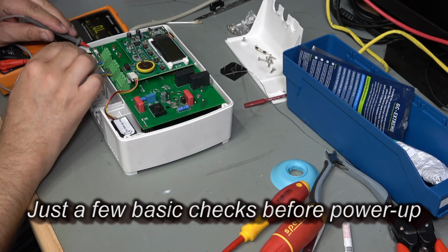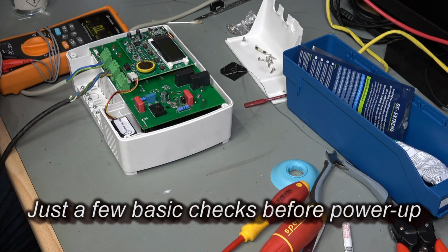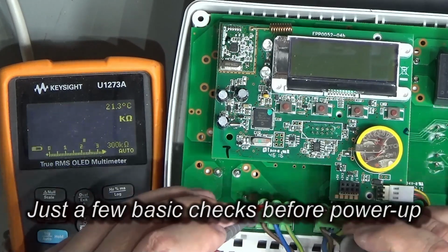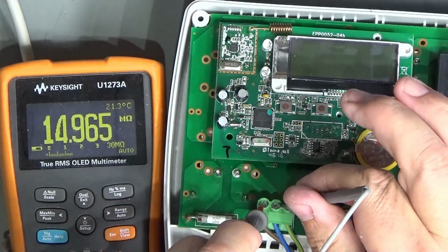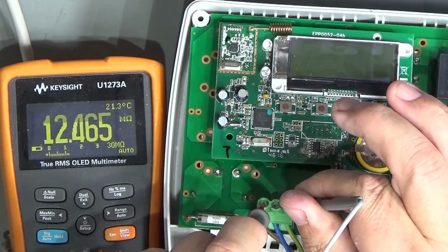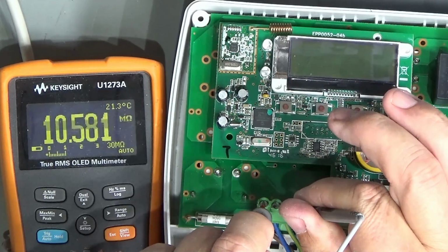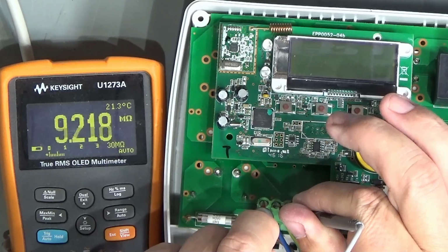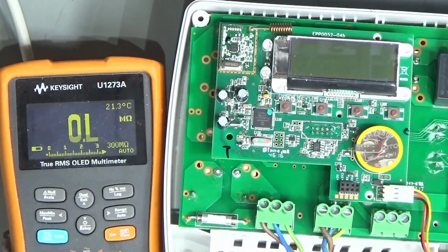Just buzz out that fuse. Perfect, lovely. There we go, so that's fine. And then we'll connect it live and neutral, and we should have a nice biggish reading. Now, because of course there's capacitance and stuff like that, this reading will gradually drop, but we can see there's a high impedance there across the mains. So happy with that.